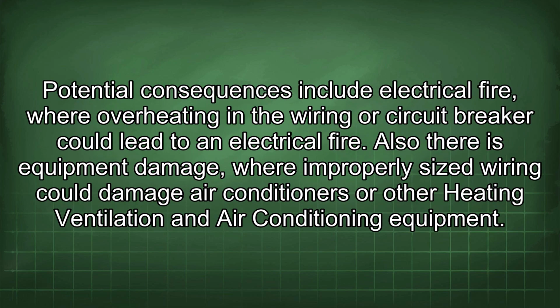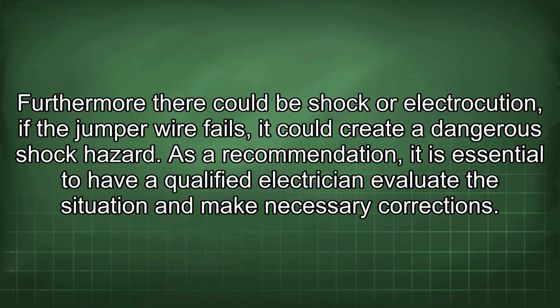Potential consequences include electrical fire, where overheating in the wiring or circuit breaker could lead to an electrical fire. Also, there is equipment damage, where improperly sized wiring could damage air conditioners or other heating, ventilation, and air conditioning equipment. Furthermore, there could be shock or electrocution. If the jumper wire fails, it could create a dangerous shock hazard.